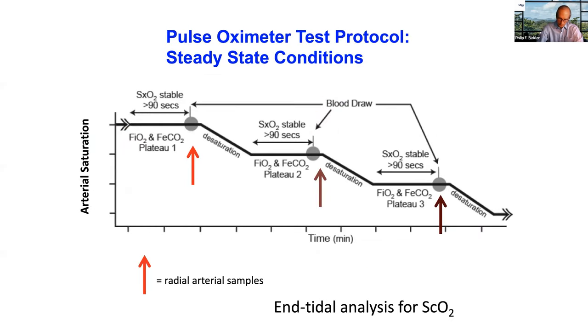Pulse oximetry produces a dimensionless number that has to be calibrated. So in order to make a pulse oximeter, you have to be able to relate the light signals to a level of saturation in the human body.